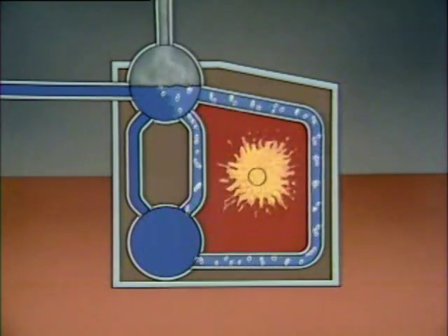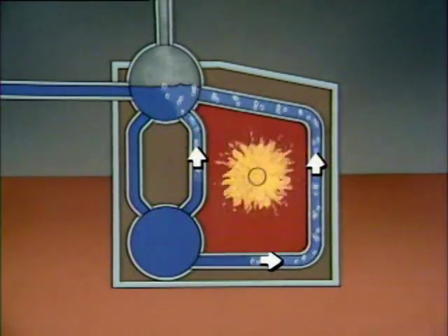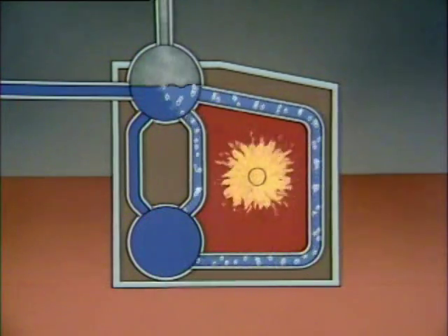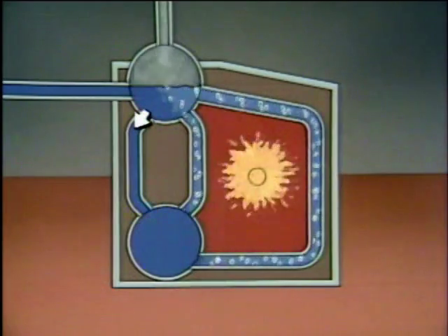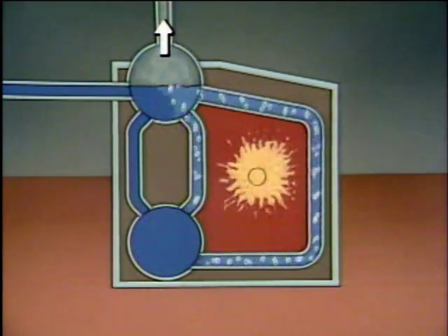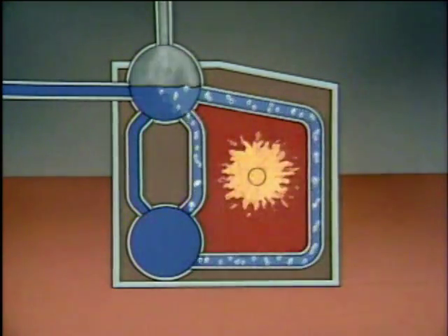As a result, the heavier, cooler water flows downward into the lower drum, and the lighter steam-water mixture flows into the steam drum. Then, as the cooler water is heated, it too becomes lighter. It rises to the steam drum and is replaced by cooler, denser water. The steam flows to the plant through the steam outlet, and the water level is maintained by the water flowing through the feedwater inlet. As long as combustion takes place, natural circulation continues. Not all water tube boilers rely on natural circulation.